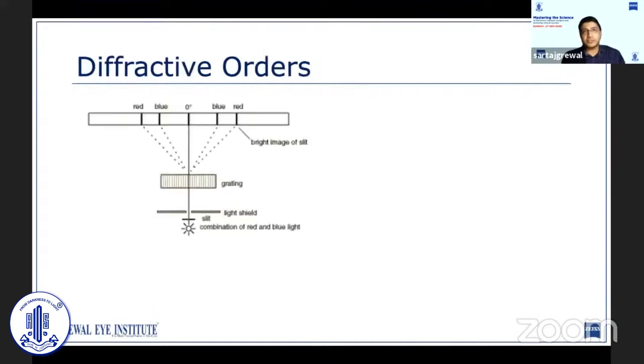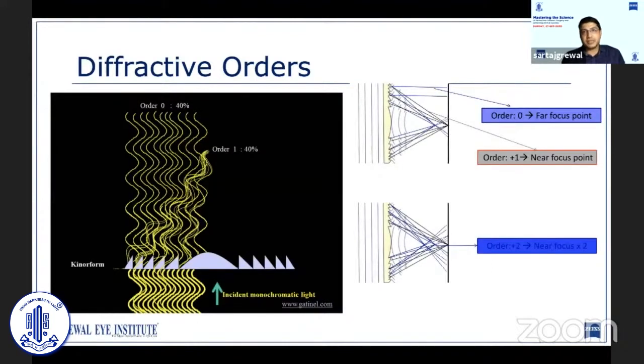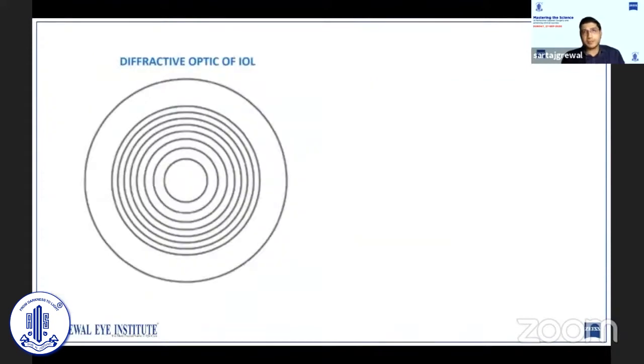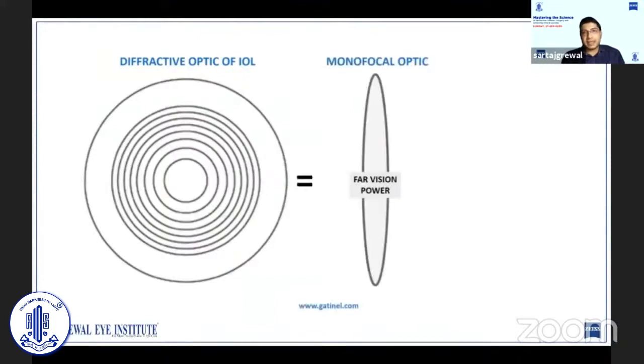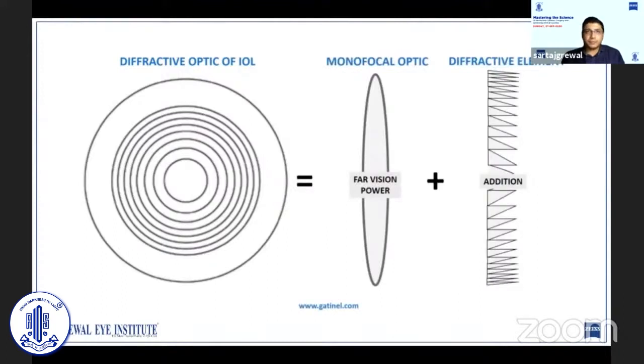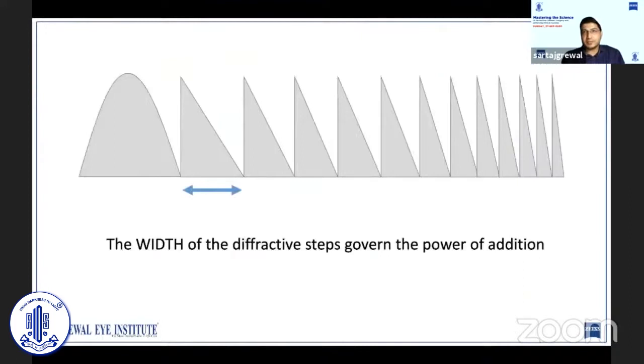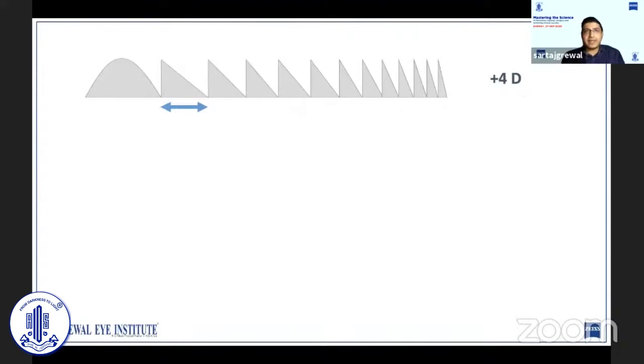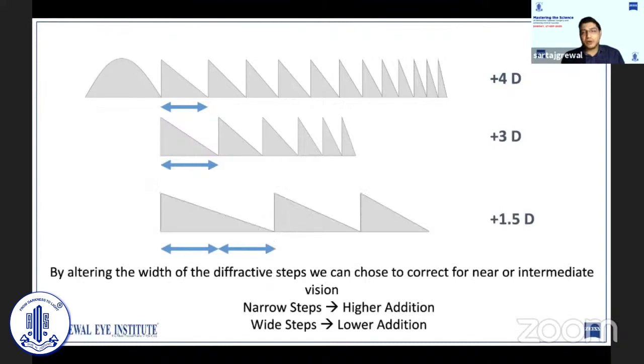During diffraction, the first bright image occurring to either side is called the first order diffraction. In diffractive multifocal IOLs, near vision is a result of the first orders of diffraction produced as a result of constructive interference as the waves spread beyond the IOL. A diffractive presbyopia-correcting IOL is simply a combination of a normal monofocal optic correcting for distance and a diffractive element providing addition for near. The diffractive element consists of numerous prism-shaped steps of varying width and height. The narrower the diffractive step, the greater the near addition; the wider the diffractive step, the lower the near addition. The width of these steps can be altered to choose between correction for near or intermediate vision.